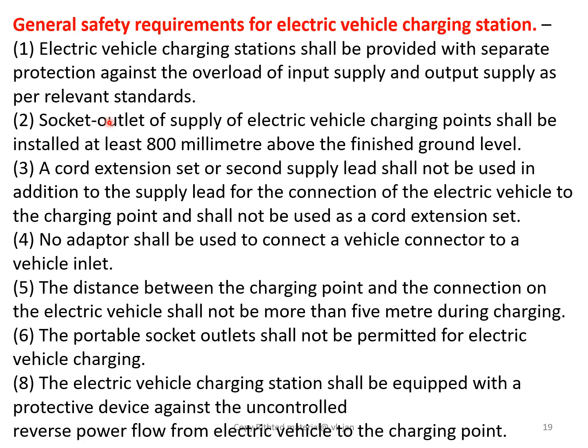Second, socket outlets supplying electric vehicle charging points shall be installed at least 800 millimeter above the finished ground level. Third, a cord extension set or second supply lead shall not be used in addition to the supply lead for the connection of the electric vehicle to the charging point. Next, no adapter shall be used to connect a vehicle connector to a vehicle inlet. Fifth, the distance between the charging point and the connection on the electric vehicle shall not be more than 5 meter during charging. Sixth, a portable socket outlet shall not be permitted for electric vehicle charging.